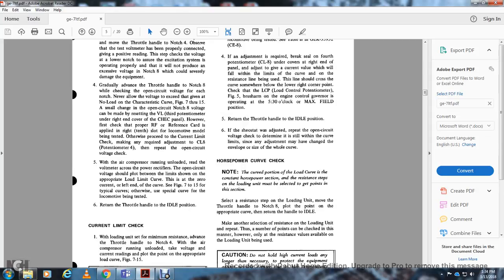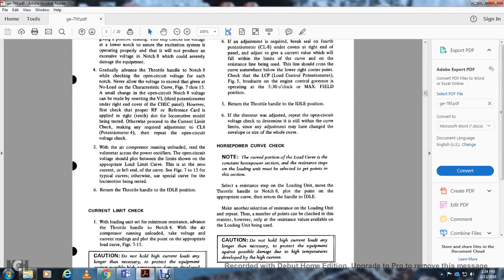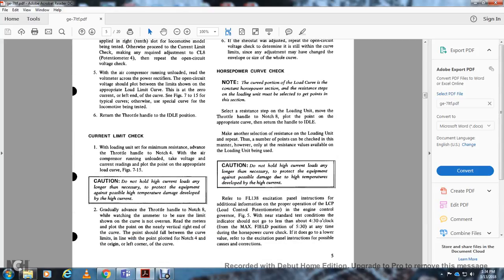Current limit check with the loading unit itself: set it with the minimum resistance and advance the throttle to notch 4 with the air compressor running and unloaded. Take the voltage and current readings at the points of the appropriate load curve in figure 7 through 15. Caution: do not hold the high current load any longer than necessary, to protect the equipment against damage from the high temperature developed by the high current. Gradually advance the throttle to notch 8, watching the ammeter to be sure the limit shown in the curve is not overrun.